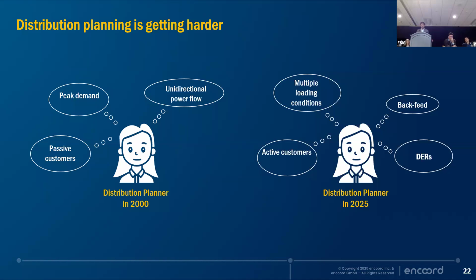But that has significantly changed over the years and continues to change. Today, a distribution planner needs to think first about multiple loading conditions that may be greatly impacted by rooftop solar PV—for instance, what they're observing tremendously in Hawaii—about how that may impact backfeed. You may now have situations where distribution feeders are generating more than they're consuming, so they could potentially backfeed into the transmission networks.